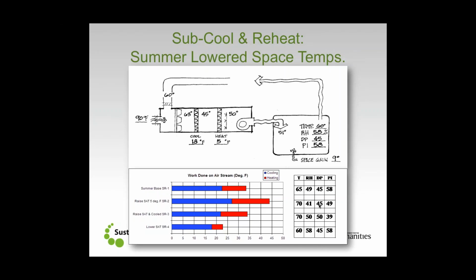So we're going to go back through and say, all right, if we get into the energy scenario, what actually happens? I've got cool air coming back. I dropped it back to a 60-degree mixed air condition. I'm still doing 18 degrees worth of cooling. There's my 45-degree dew point. But notice now that because my temperature is significantly lower, the amount of reheat that I have to do is correspondingly less.